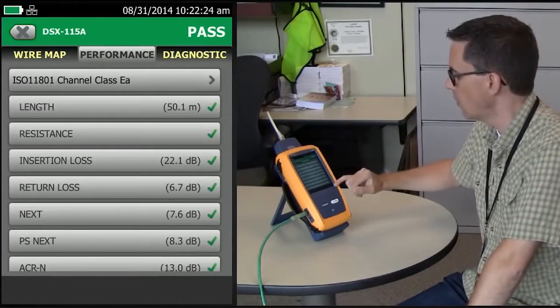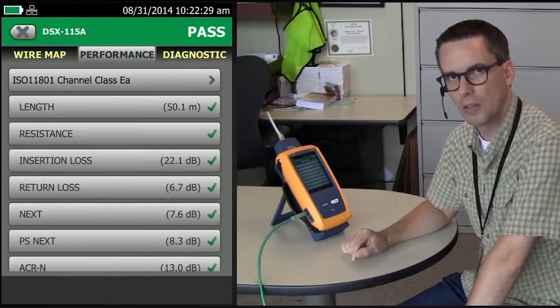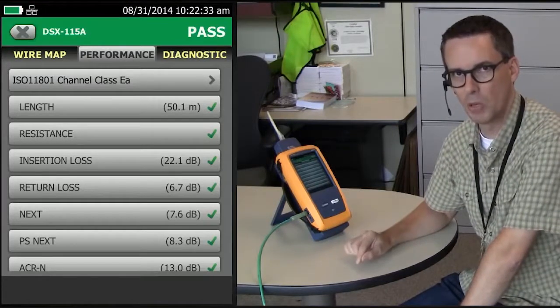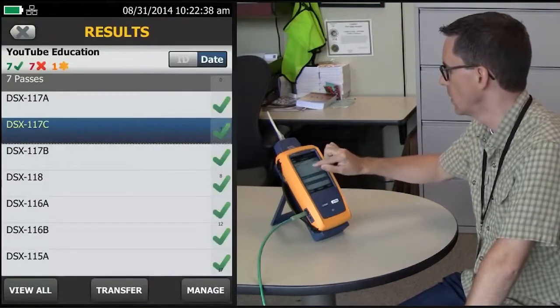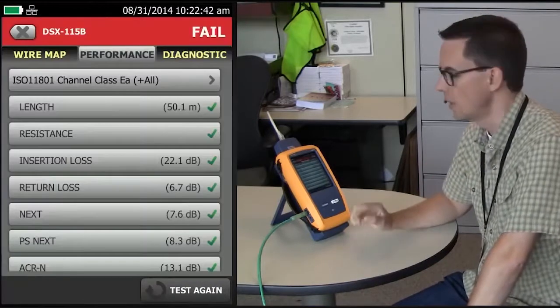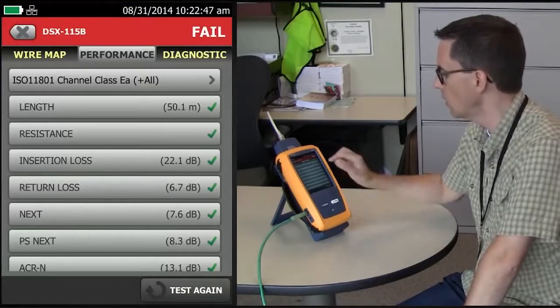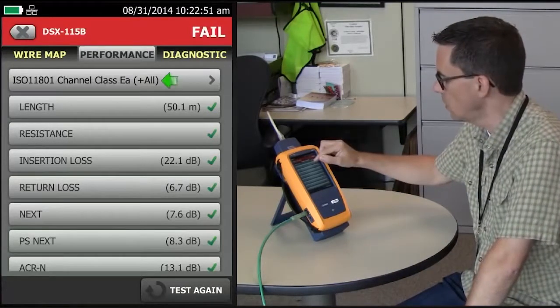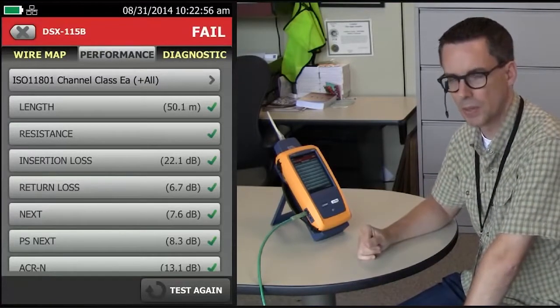So everything here passes. Let's redo this test again, but now include that additional TCL measurement, which is required in the laboratory but not required in the field. I've got it stored on the instrument here, so let me go back up. This is exactly the same link, same cords, same everything. But now we've done this plus all tests — our new test limit, which includes all the measurements that this tester can do, including resistance and balance.